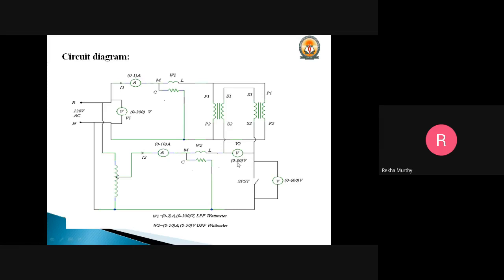So here the voltmeter we are going to use is 0 to 600 volts, and we are going to connect one SPST switch in between, because when this SPST switch is open, we are going to find out the core loss, that is, the open circuit test will be conducted, and when the SPST switch is closed, it will be the short circuit test. Okay, fine. So after that we are going to complete this loop, and also we need to connect the voltmeter across this SPST switch.